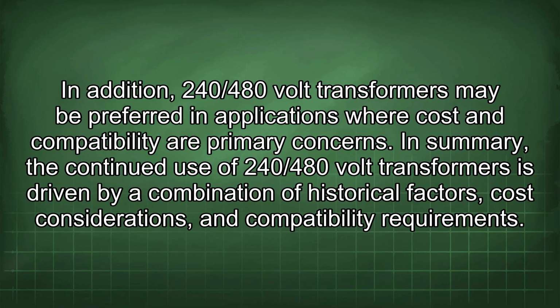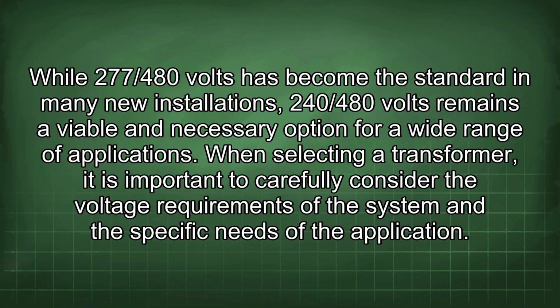In summary, the continued use of 240/480 volt transformers is driven by a combination of historical factors, cost considerations, and compatibility requirements. While 277/480 volts has become the standard in many new installations, 240/480 volts remains a viable and necessary option for a wide range of applications. When selecting a transformer, it is important to carefully consider the voltage requirements of the system and the specific needs of the application.